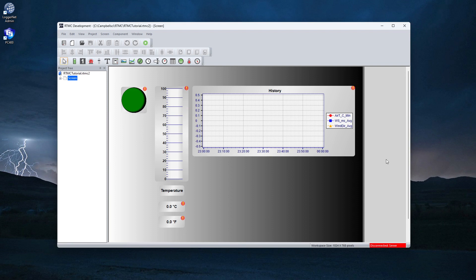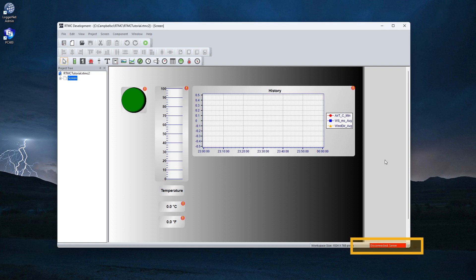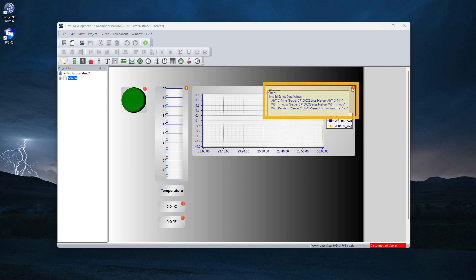Here's a troubleshooting tip: if an exclamation point appears at the upper right of a component, there is a problem with the linked data value. The main cause of this is that scheduled data collection is not running. In this case, I can see in the lower right that the LoggerNet server is disconnected. In development mode, hovering the mouse pointer over the box for a few seconds will display a pop-up hint about the error RTMC has detected.